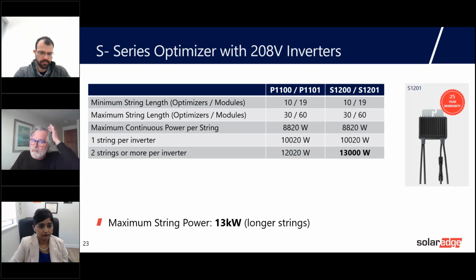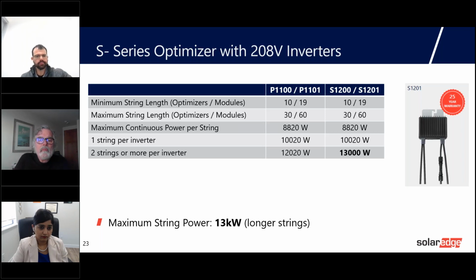And then the maximum, we do have a theoretical maximum here of 30 optimizers and 60 modules. I say theoretical because we really determine maximum string length based on power rating, which is the last three rows that I'll talk about in a second. The theoretical maximum you would probably never reach unless you had modules that were really fairly low power rating, much lower than we typically see today. So the maximum continuous power per string for our 208 volt inverters is based on a fixed string voltage of 490 volts DC. If you take 490 volts times 18 amps, you come up with this base power level per string of 8,820 watts. And this would be considered a maximum string length with no string oversizing. It's really just a baseline maximum string length.